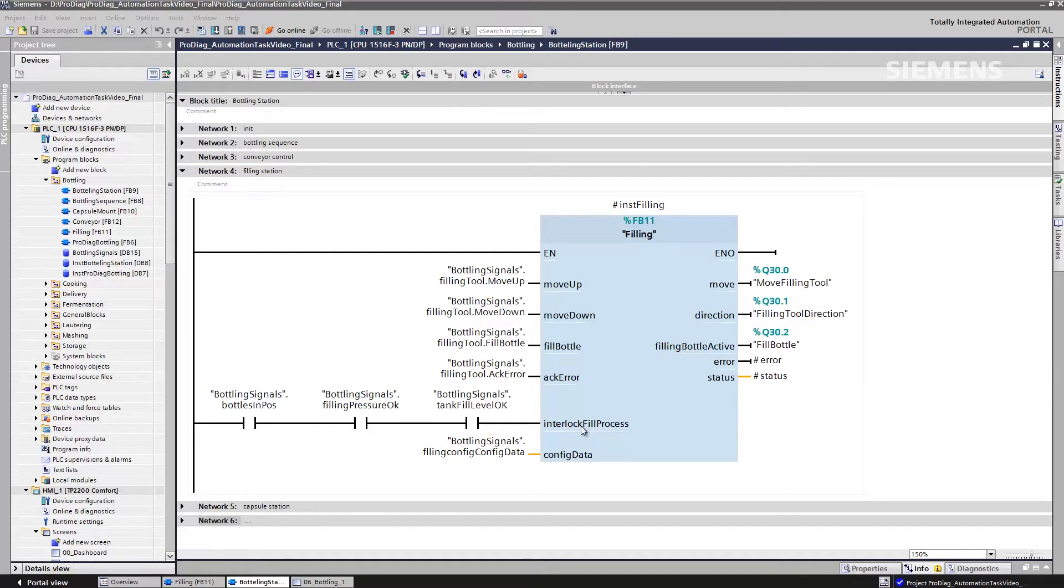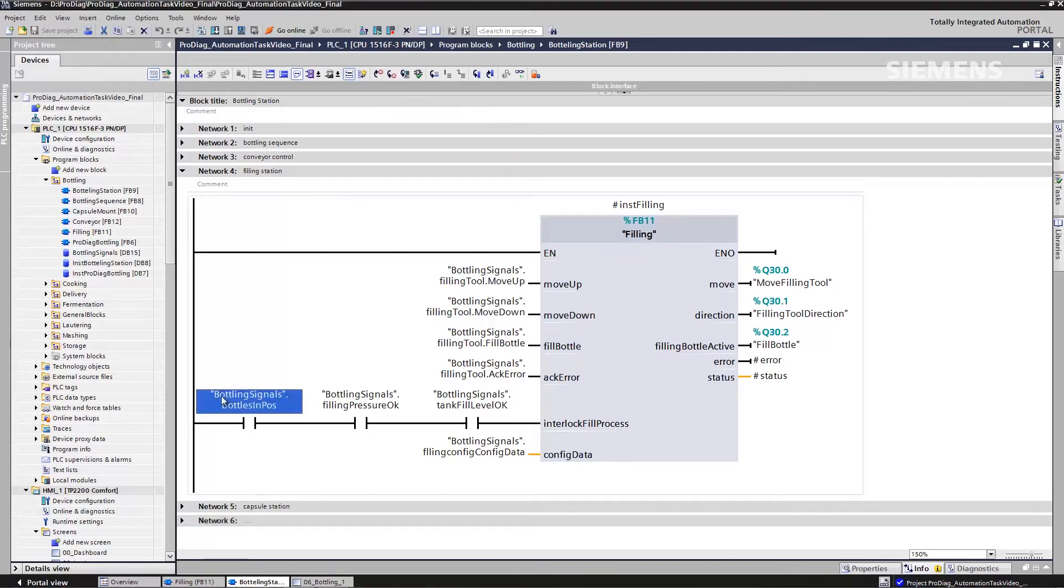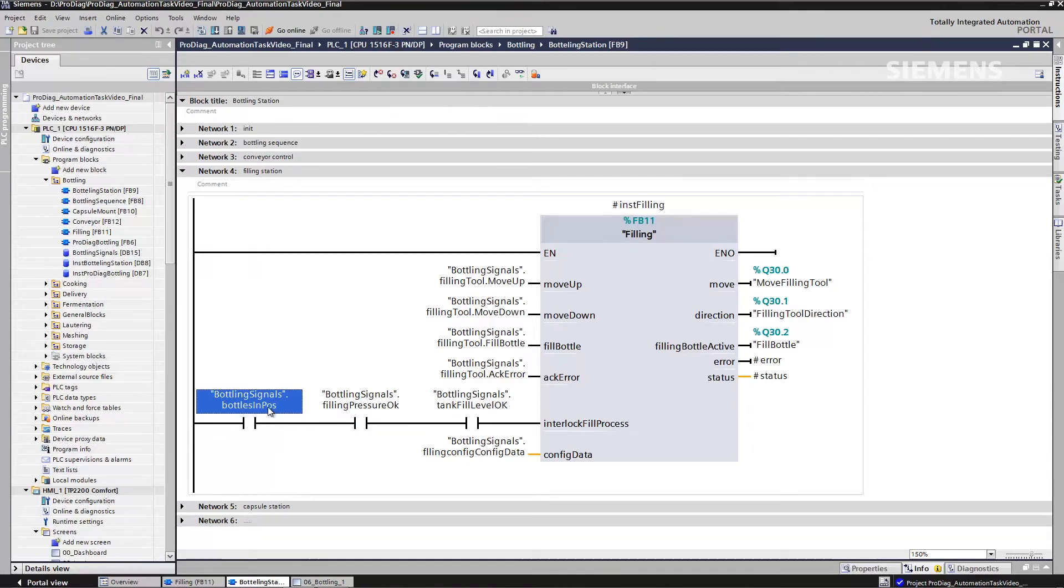that's my operand parameter that I monitor for interlocking purposes. It's my release signal. And why was that process not released? Because an upstream interlock condition had not been met. Here, for example, the bottles are not in the correct position. Or, as in our case, there is simply not enough pressure available to fill the bottles.